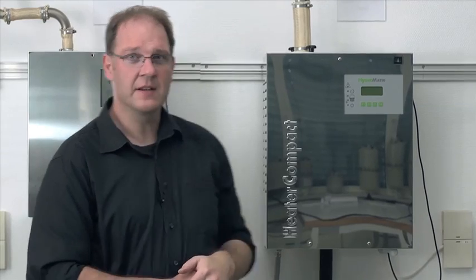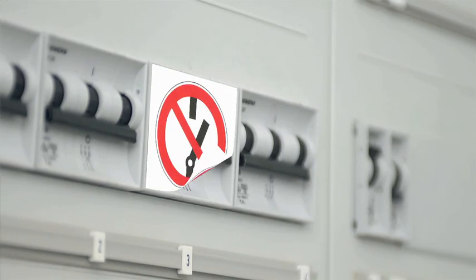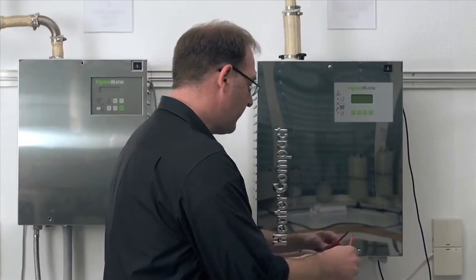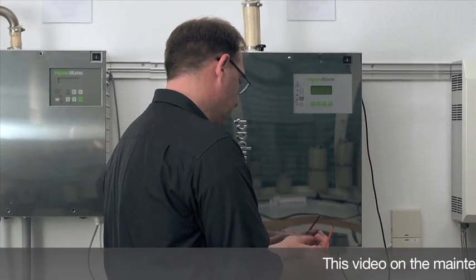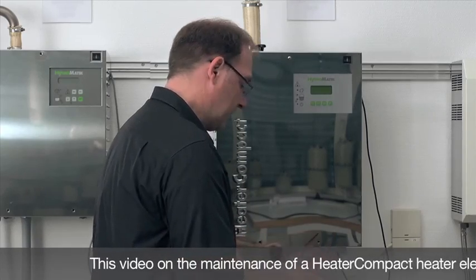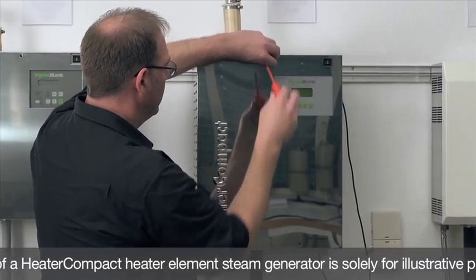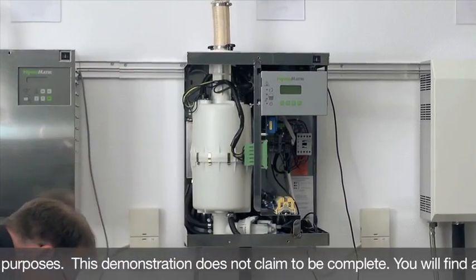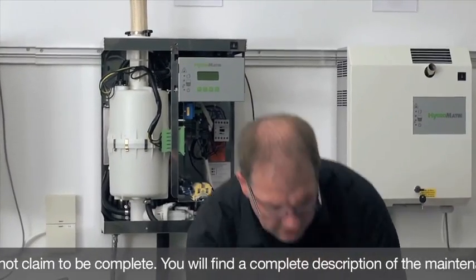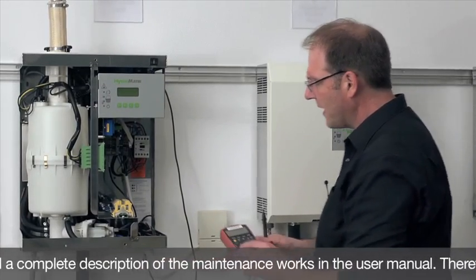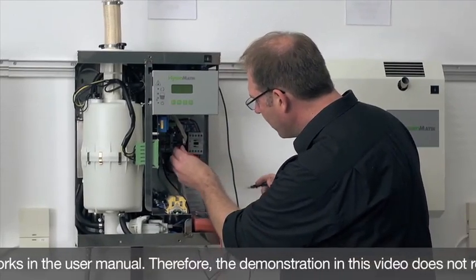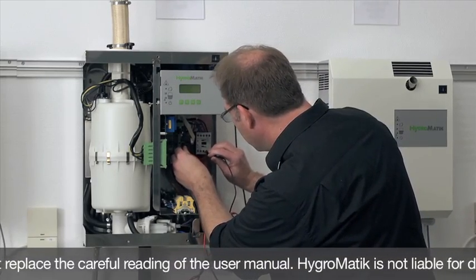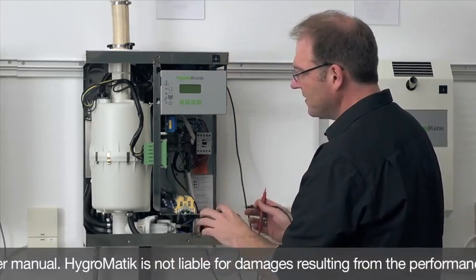Next, I will disconnect the unit from the power supply and protect it against being restarted. The cover is mounted to the unit with three screws. I am going to undo them now and then I can just take off the cover. The unit is open, but before I carry out the maintenance, I would like to reassure myself that there is really no electric current anywhere. I will check for voltage disconnection at all points of the main contactor. There is no voltage detected anywhere, then I can continue with the maintenance.